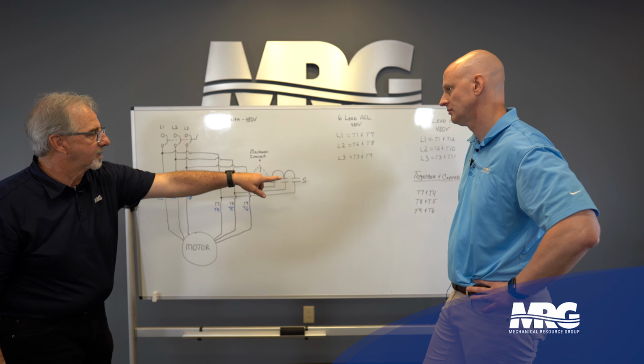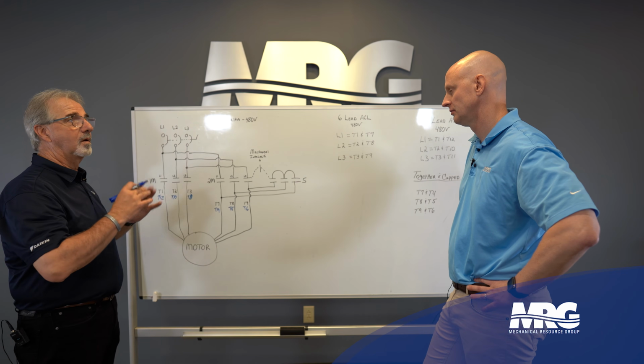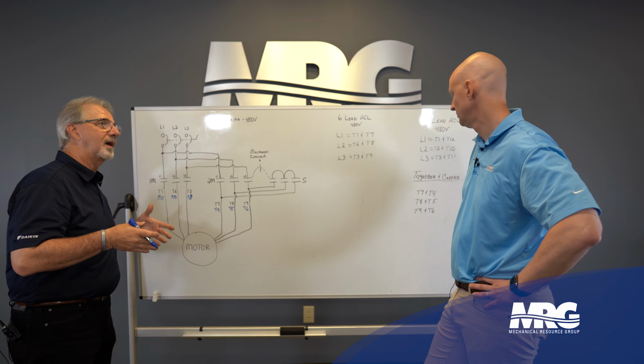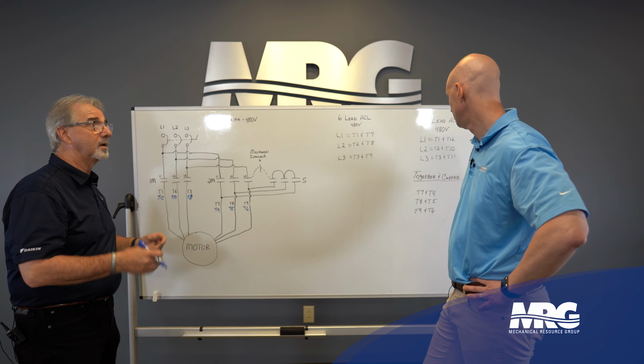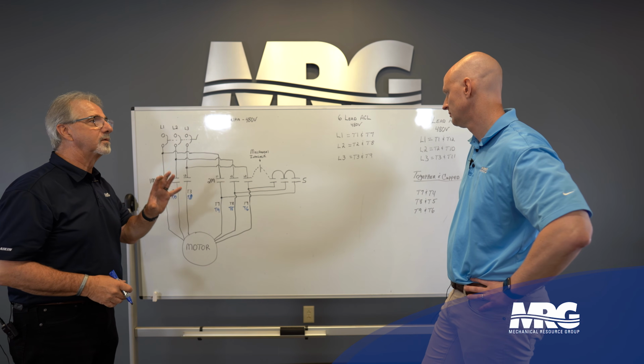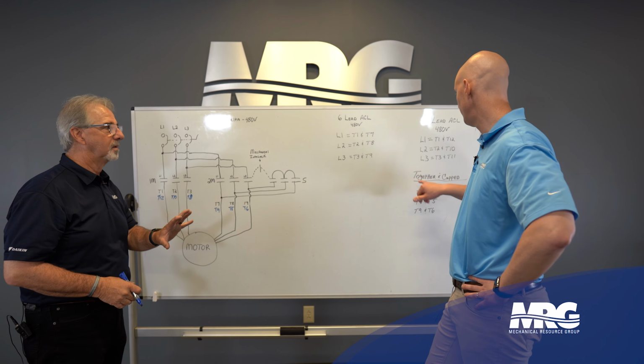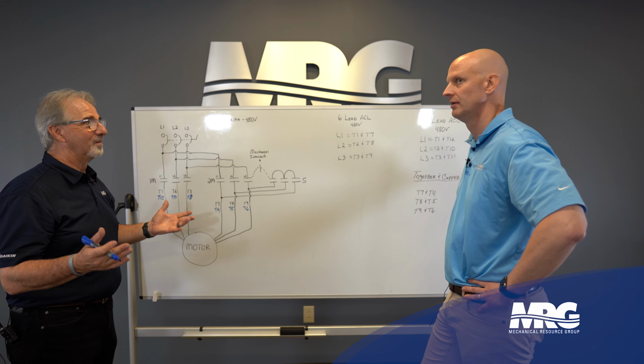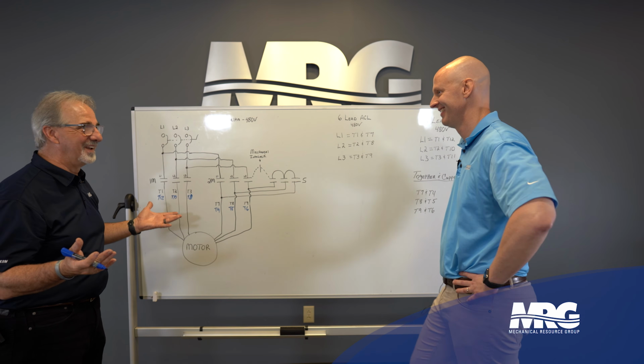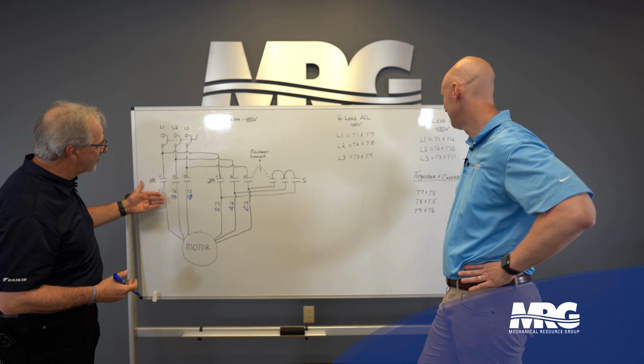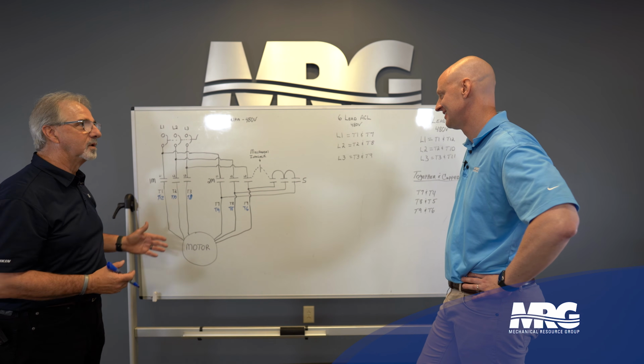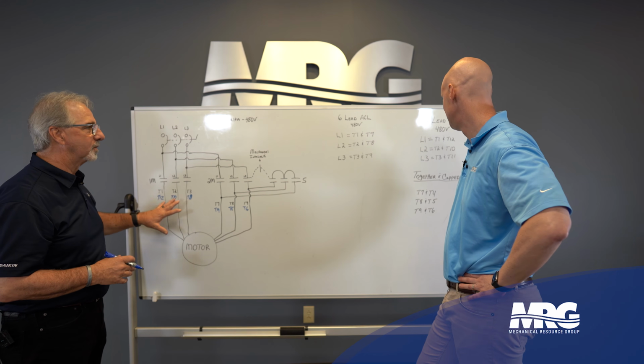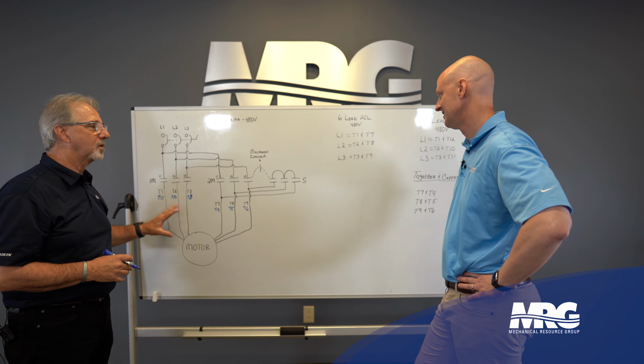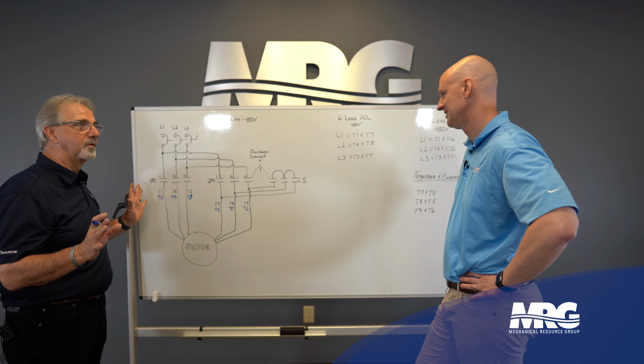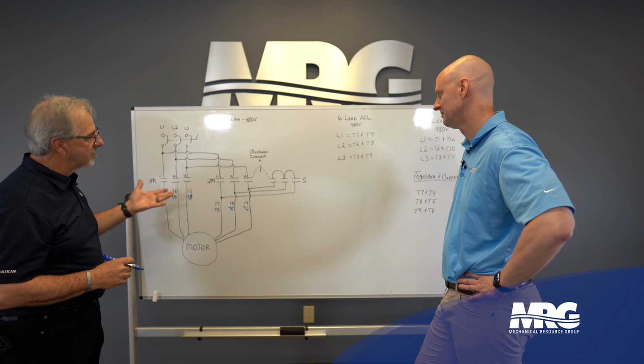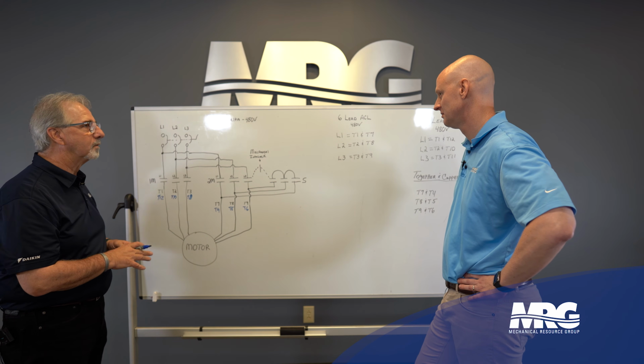you see how these are together and capped? What I said is, all right, now we're not going to cap them. We have to have them in the circuit now because I'm Y-Delta. This is why Y-Delta gets really confusing, especially when you're right together and capped. If I'm running across the line, I'm going to be together and capped. So this is why Y-Delta becomes really important when you're hooking up a 12-lead motor on a Y-Delta starter. Thank God we don't see a lot of them anymore. But this is what you have to be very careful with.